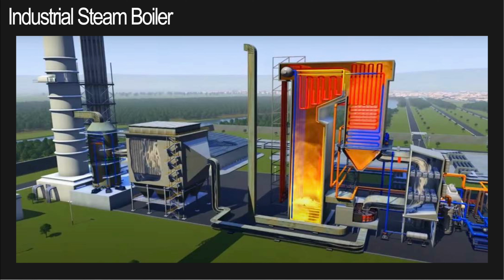Now, the water itself is going to be preheated in something called a calorifier. That's basically what the calorifier is. It meets the hot flue gases, the basically spent flue gases before they go to the vent stack. It gets preheated. Sometimes you call it the economizer. And it flows into these sections. So here is still water.